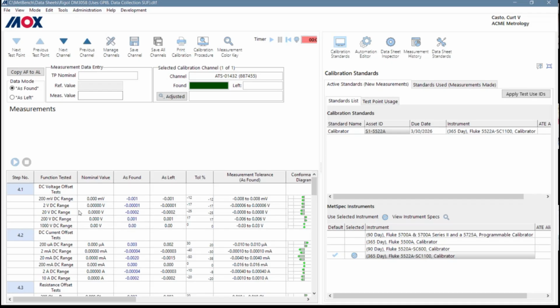Have you found it to be the same, easier, or harder to build data sheets in other systems from what you just saw? Yes, this made it very simple. I would say this is probably one of the easiest I've ever seen being created so quickly. Plus the uncertainties too, right? I know some of the software creates data sheets, but they don't really handle the uncertainties. They just handle the data points and tolerancing. And then you're usually manually typing in the uncertainty, or you have to do some kind of scripting for it to know how to do the uncertainties, right?